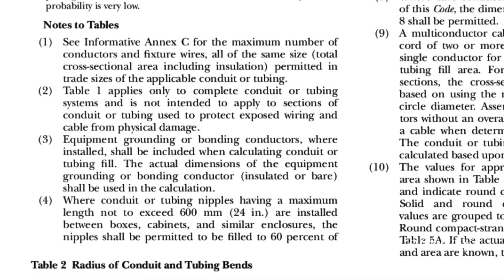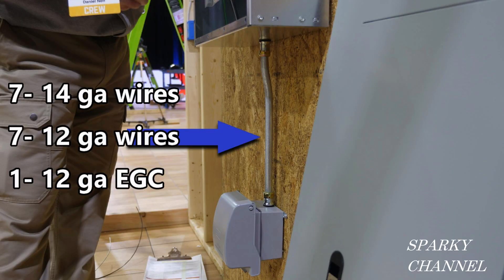Once again, we'll go to Notes to Tables, but this time to Number 3. Equipment grounding or bonding conductors where installed shall be included when calculating conduit or tubing fill. The actual dimensions of the equipment grounding or bonding conductor, insulated or bare, shall be used in the calculation. So that means we have seven 14-gauge wires and eight 12-gauge wires. Let's check it out.